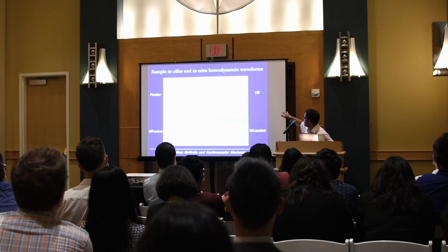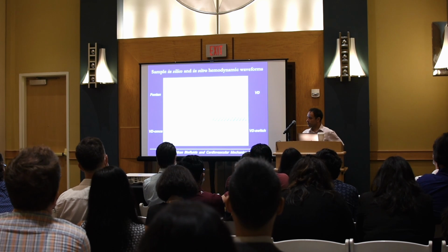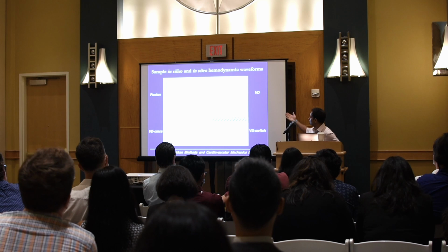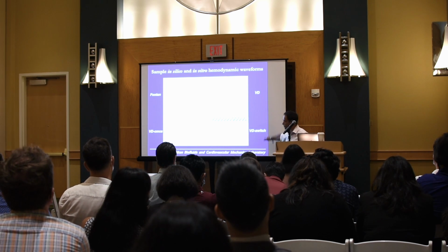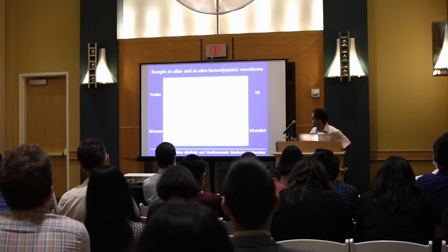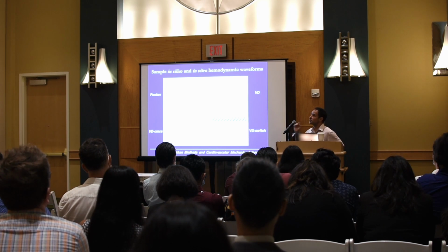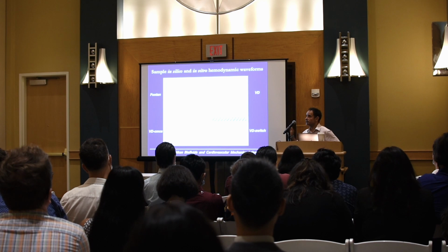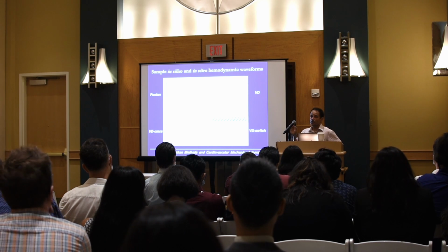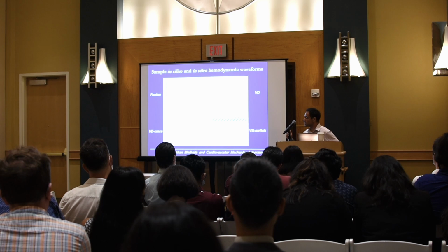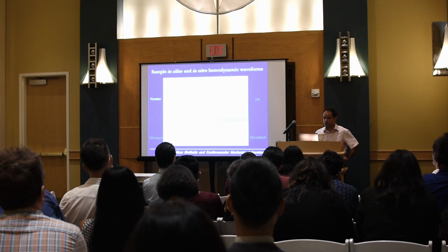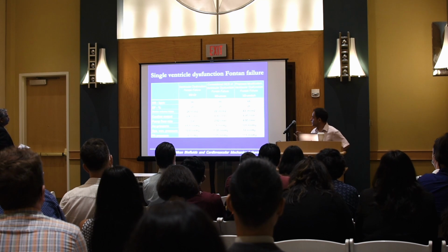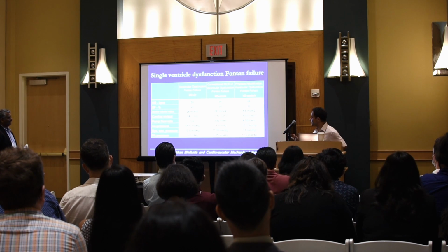So here are some of the waveforms we compared between computations and experiments for the different cases that we studied. And this is the proposed configuration, VAD switch. We have some oscillations because in the in vitro test, at the exit of the ventricle assist device there is a pressure transducer which picks up signals from our in vitro system. Okay? So I think the time is coming.